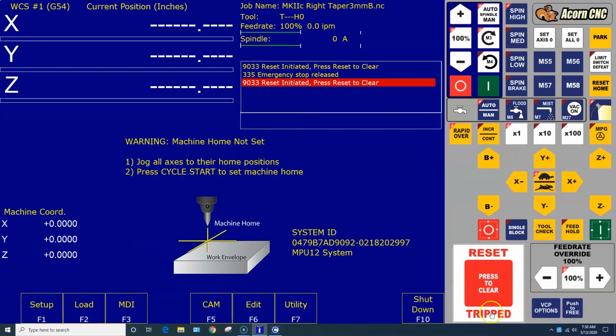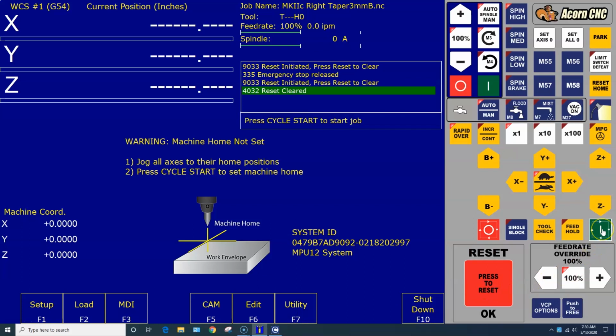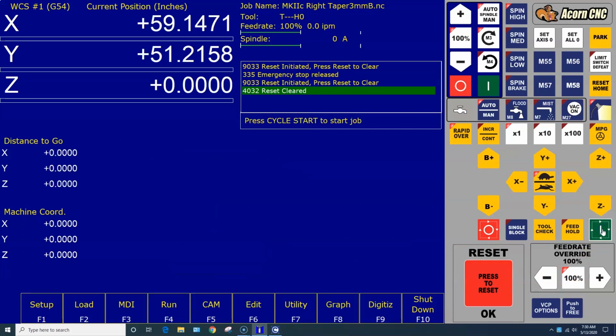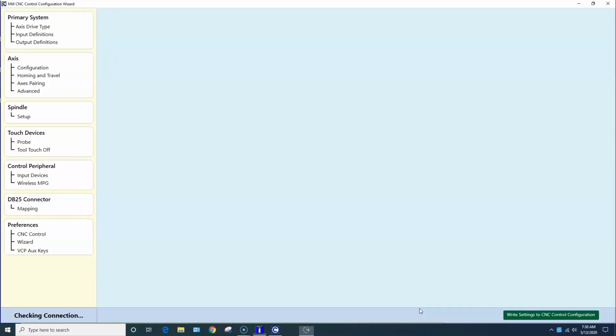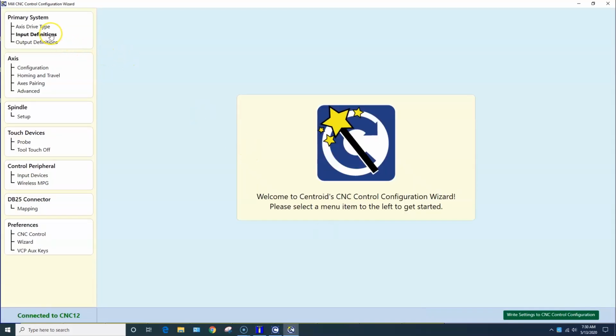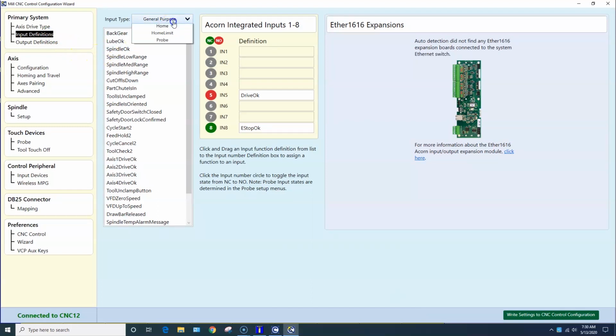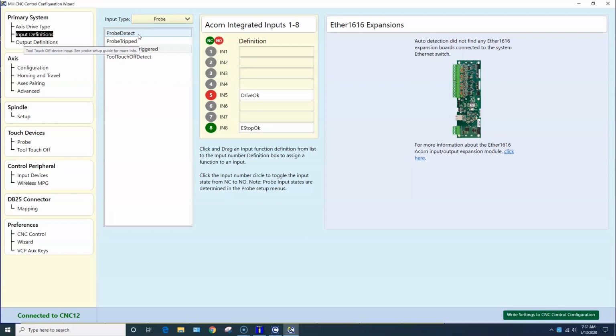So I'm going to go ahead and reset my bench test rig here. Set home just for the sake of doing it. Let's go ahead and go into the wizard. Okay, the first thing we're going to want to do, input definitions. We want to click on probe. We're going to want to drag probe detect to input 6. So we're going to left click, hold, drag it to input 6, and then we're going to want probe tripped. Click on it, drag to input 7. Let's double check. Per the manual, probe detect is on input 6 and probe tripped is on input 7.